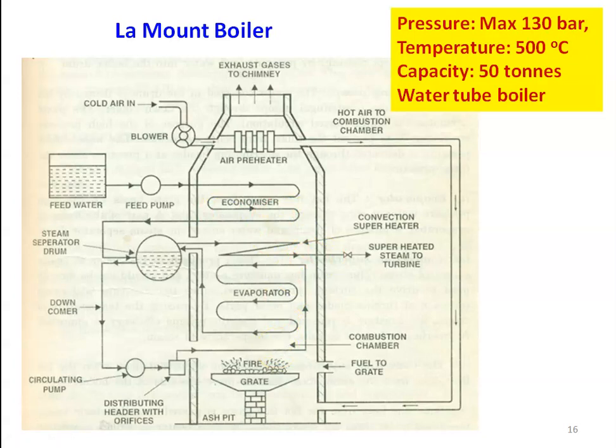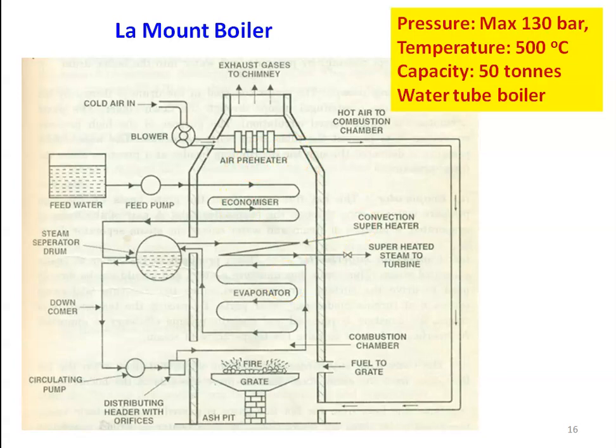As the gas flows upward, first the evaporator absorbs the heat energy. The evaporator is the device which converts water into steam. Then the steam goes to the superheater where it is superheated using the heat energy. Then the gases go to the economizer, where the heat is utilized for heating the incoming feed water. So, the economizer is used for heating incoming water.